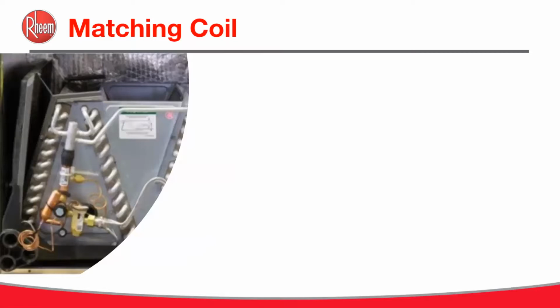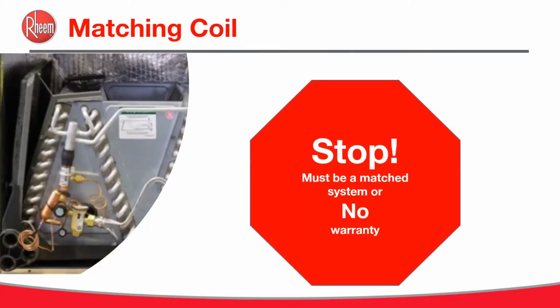So matching the coils. This is the last item. Coils must be properly matched to ensure proper heat transfer capabilities. An improperly matched coil can cause abnormal heat transfer, pressure switch trips, capacity issues, and finally, compressor failure. Approved matches can be found on the Rheem spec sheet and on the AHRI website. Stop. It must be a matched system or it's going to affect your warranty.